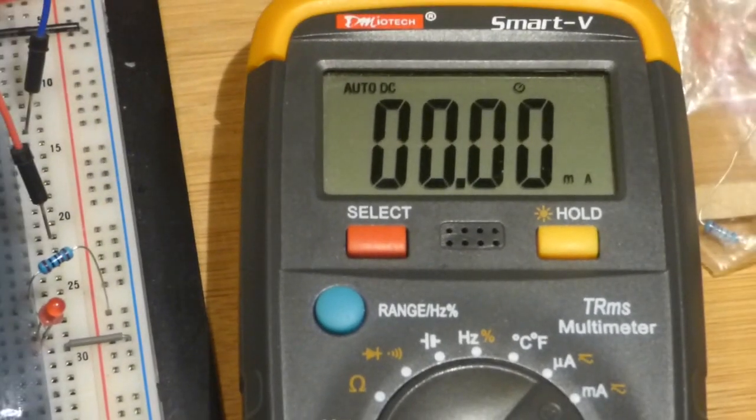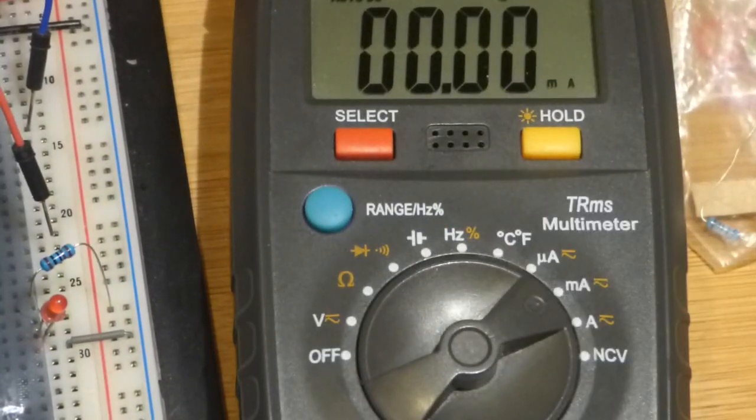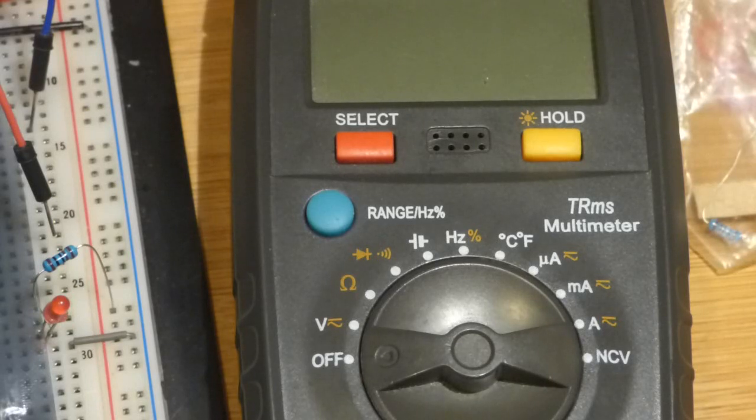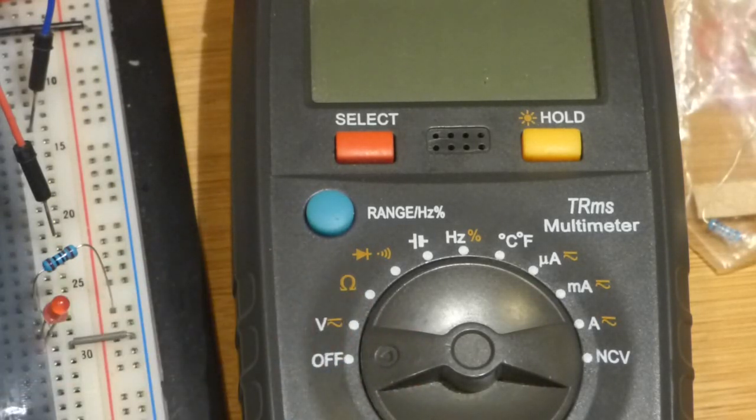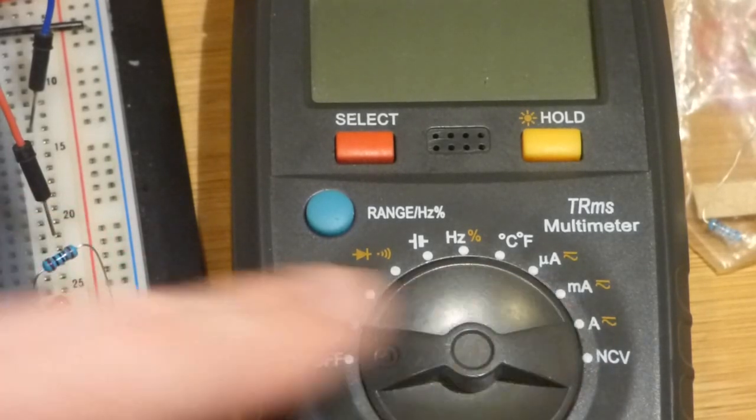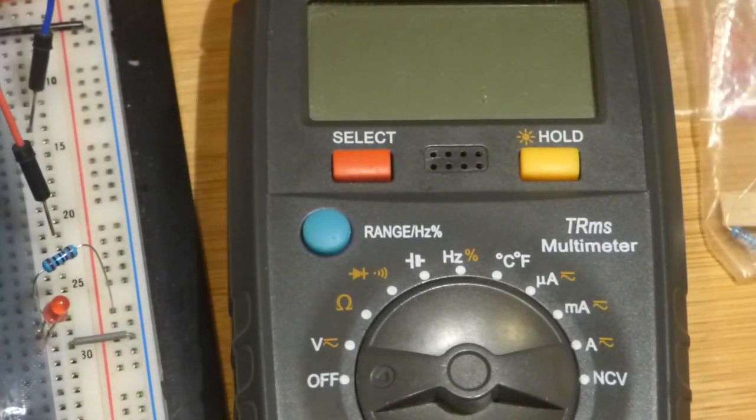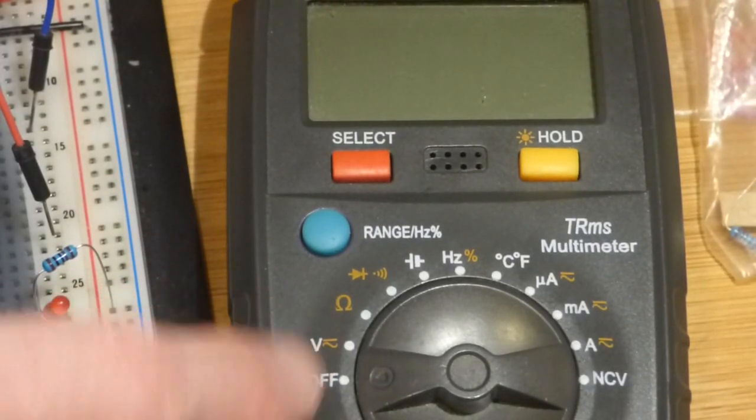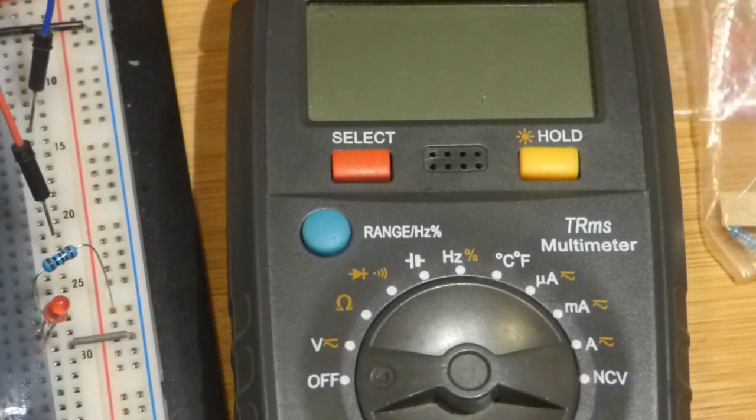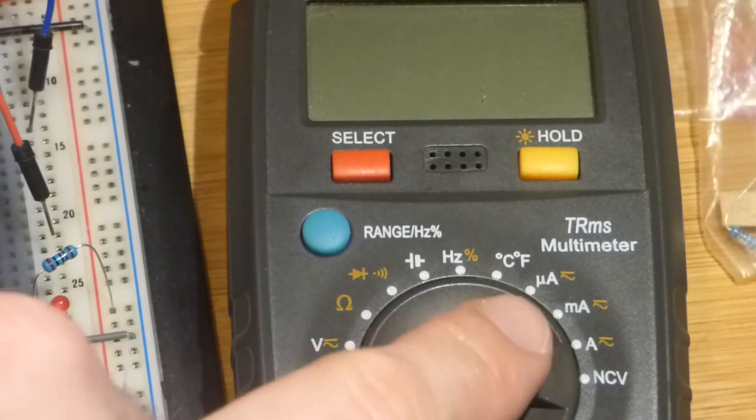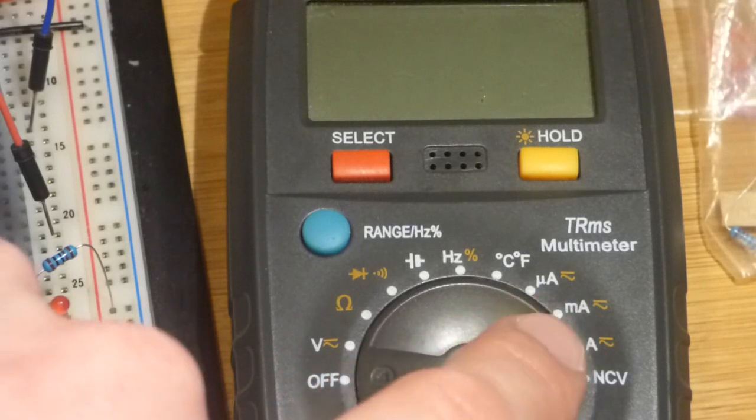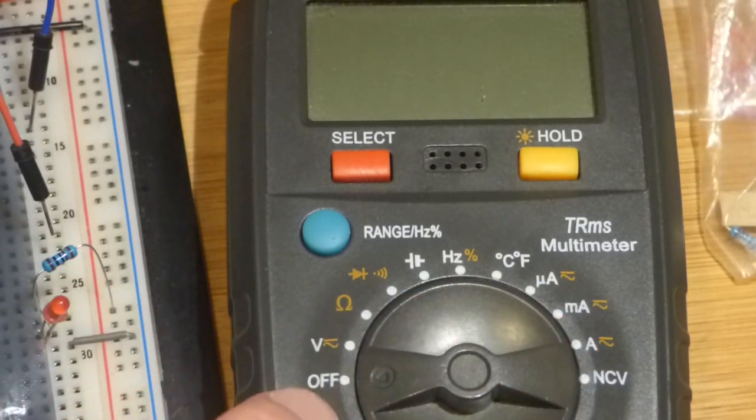Before I go, actually, the meter is set to measure milliamps. Before, as I said, you have to be careful when you're measuring milliamps. So make sure you turn it off right after you're done measuring current. Turn it off, set it to voltage. Voltage is safe too, but don't leave it on milliamps. A lot of times I see the meters on, I try to take a voltage measurement right away. The voltage is safe to measure, but milliamps of current, if you measure a power supply directly, it will probably blow a fuse in the meter. So it's a good habit to, as soon as you're done measuring current, get it off of current, either voltage or off completely.